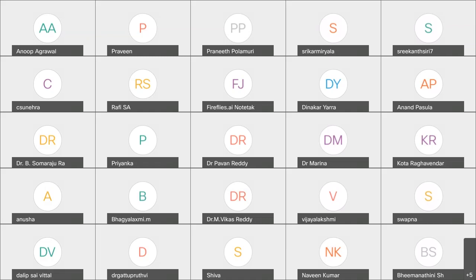PEEP is positive end expiratory pressure, given during the expiratory cycle. But BiPAP involves two levels of positive airway pressure. BiPAP traditionally is actually a mode from the Respironics company, so it's basically a trade name, not truly a mode. You can call it bi-level pressure support, or BIPS. There's a lot of terminology here. CPAP is continuous, same pressure during expiration and inspiration. If you use two different pressures, one for inspiration and one for expiration, we now routinely call that BiPAP. That is the difference.